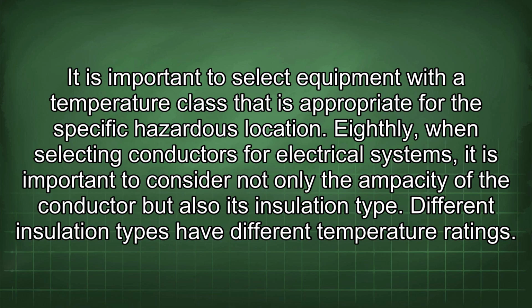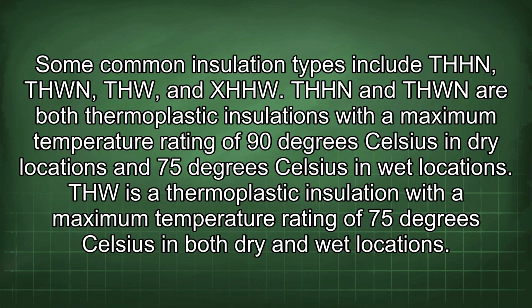Eighthly, when selecting conductors for electrical systems, it is important to consider not only the ampacity of the conductor but also its insulation type. Different insulation types have different temperature ratings. Some common insulation types include THHN, THWN, THW, and XHHW. THHN and THWN are both thermoplastic insulations with a maximum temperature rating of 90 degrees Celsius in dry locations and 75 degrees Celsius in wet locations.